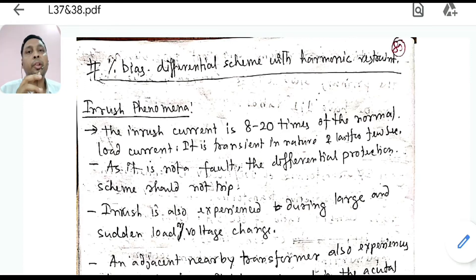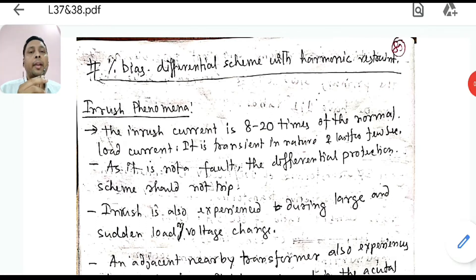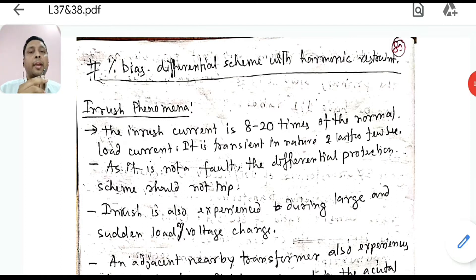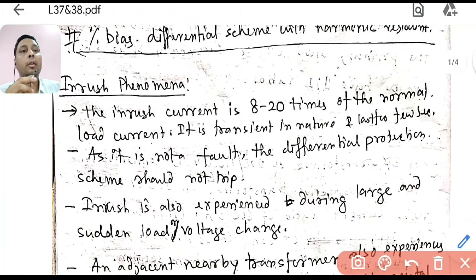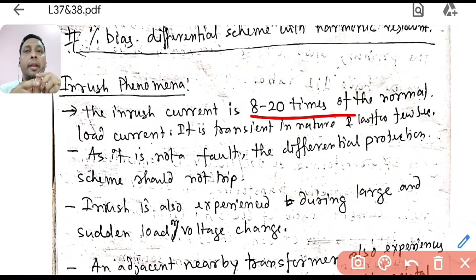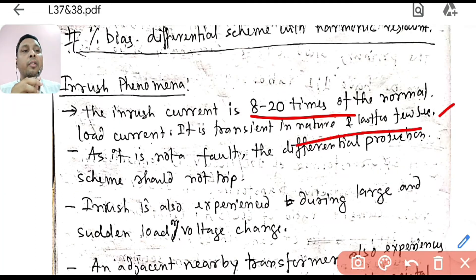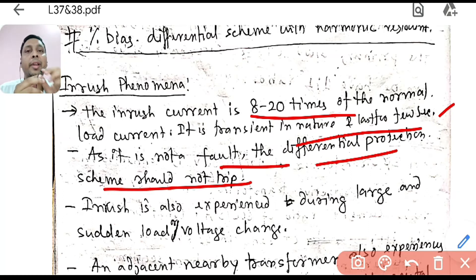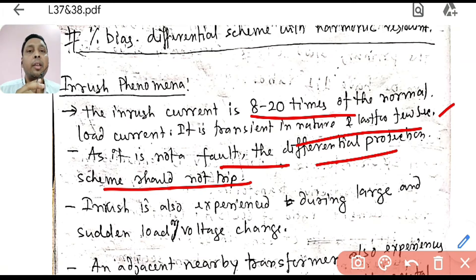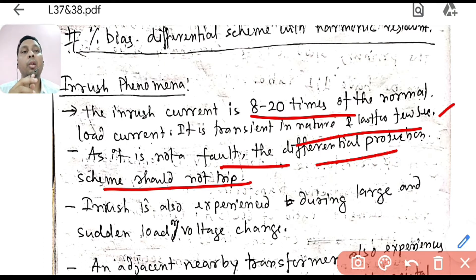This scheme came into the picture due to the inrush phenomena. Inrush is a current which is 8 to 20 times your normal current. It is transient in nature and lasts for a very few seconds. The differential protection should not trip for it — it should not treat it as a fault — because the input current will be very high while the output side is unloaded.